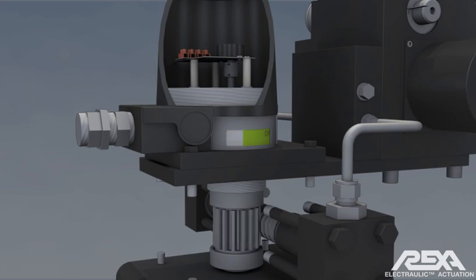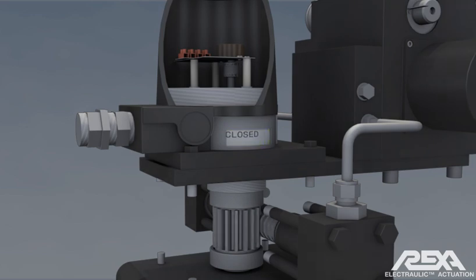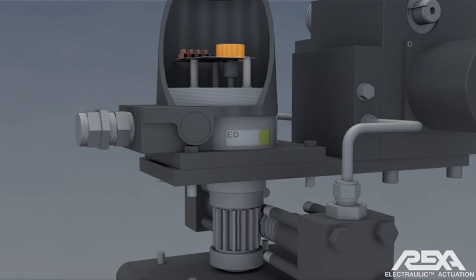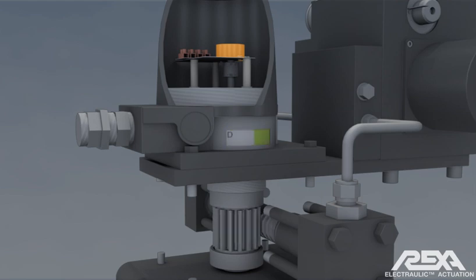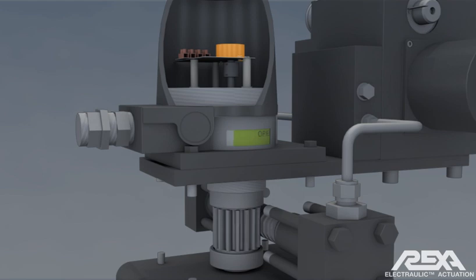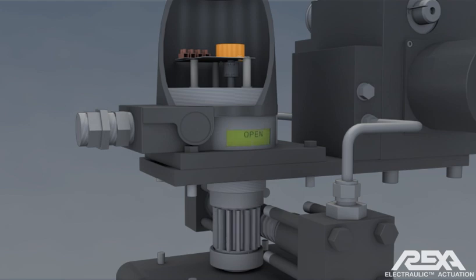The feedback module contains a potentiometer connected to the pinion. As the pinion rotates, it will also rotate the potentiometer, adjusting the signal from this device which represents the position of the valve.